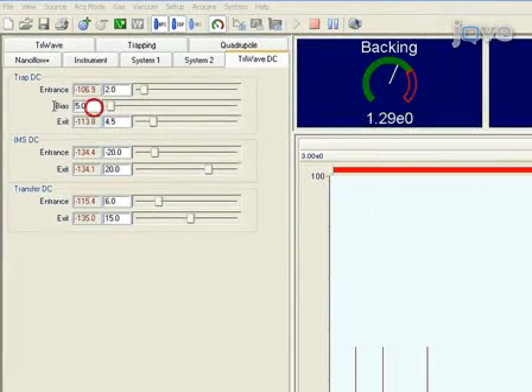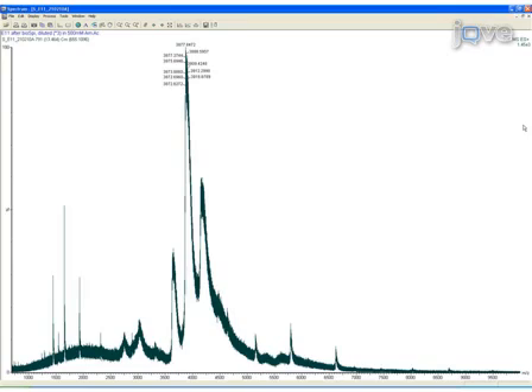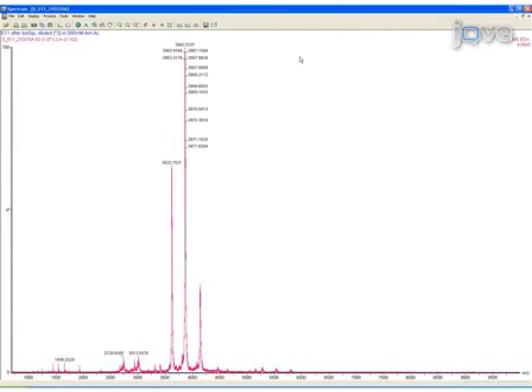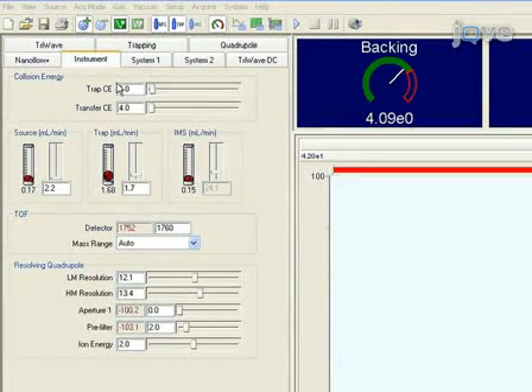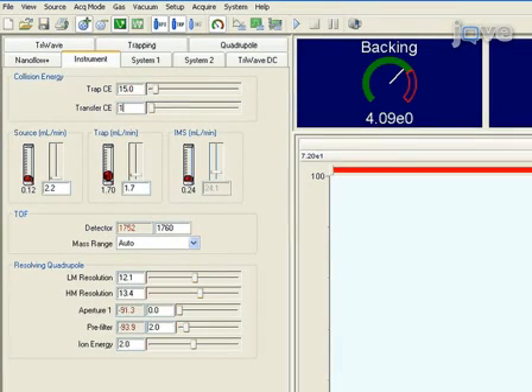To improve desolvation and strip off residual water and buffer components, increase the bias voltage and the gas pressure in the collision cell. Typical bias voltages are within the range of 10 to 100 volts with a trap gas flow of 1 to 10 milliliters per minute. Perform this carefully to prevent dissociation of the complex. Adjust trap and transfer collision energies. Often, higher voltages, usually within the range of 10 to 30 volts, are required for transmission of high-mass ions.